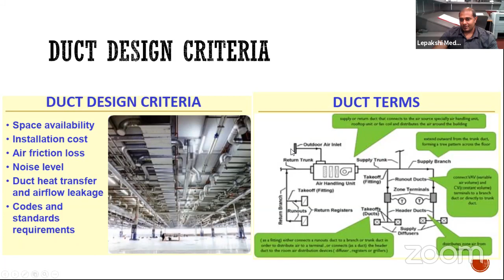For instance, now you're putting so much heat or so much cooling into this processed air, right? You can't just exhaust all of it because you already spent so much money on it. That's what this recirculation is all about. So a portion of it is exhausted, but mostly it's recirculated. To compensate for the exhausted portion, you have to take in some outside air.